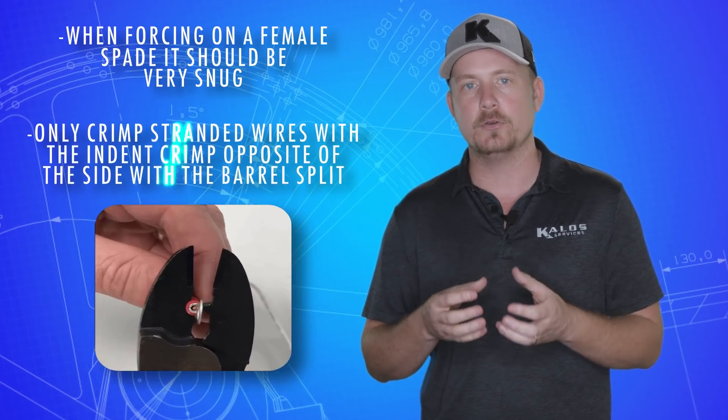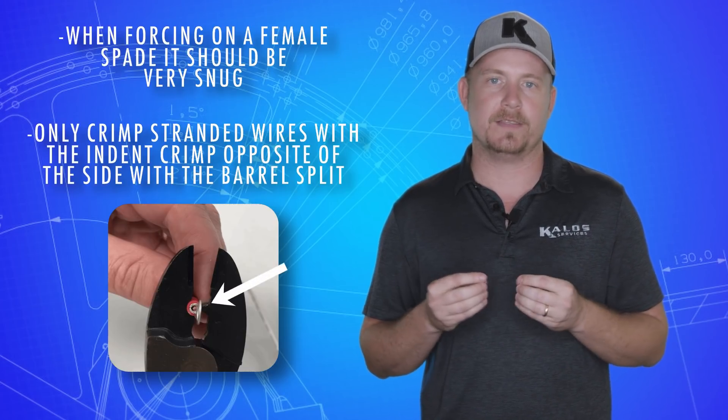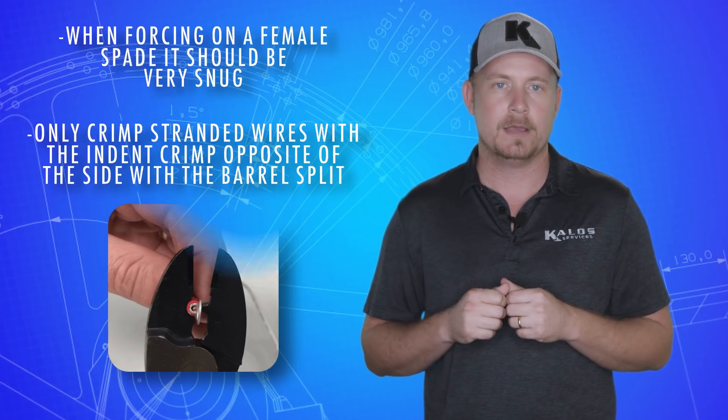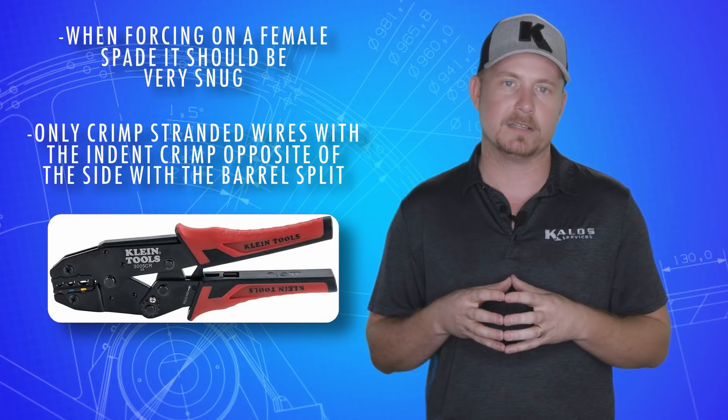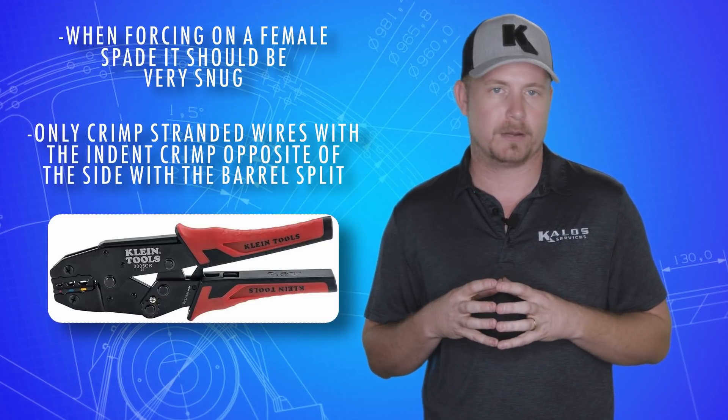Position the jaws so that the indent crimp is made on the side of the connector opposite the split in the barrel. Even better is to use a crimper specifically designed for insulated terminals that compresses the entire barrel. I prefer to use ratcheting crimpers.